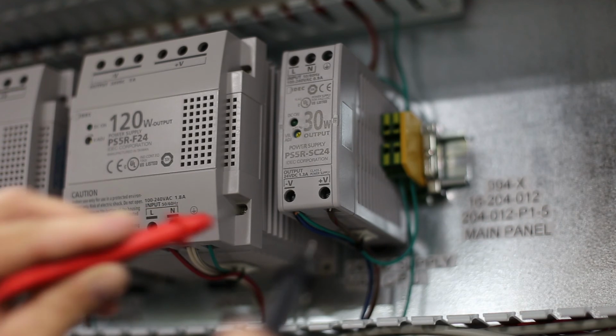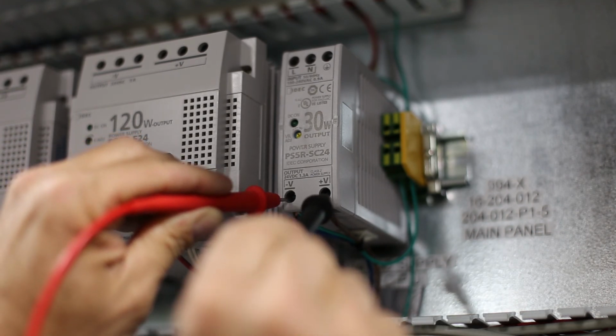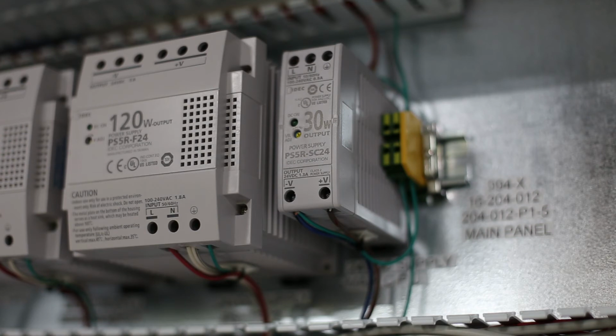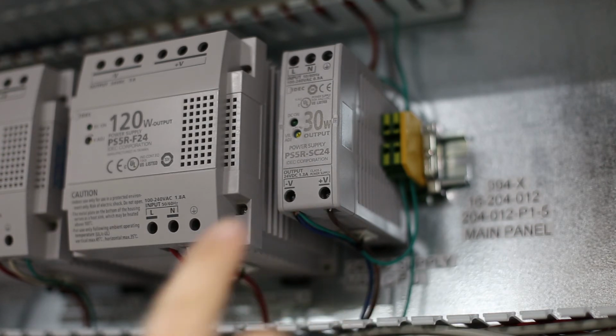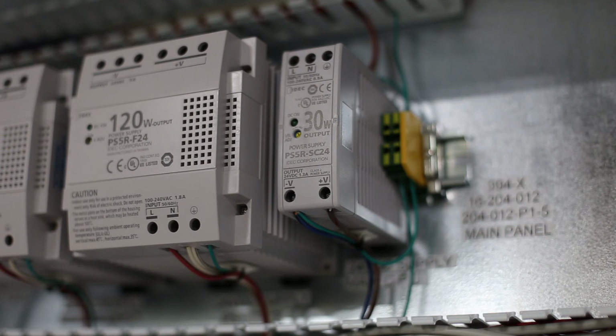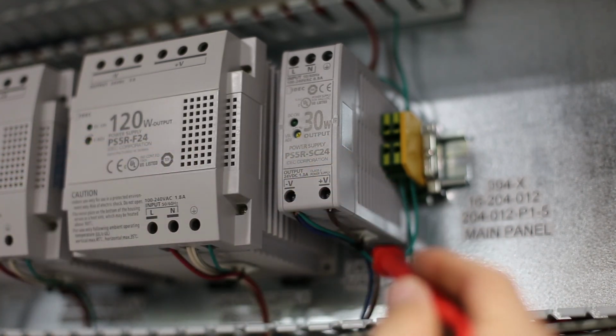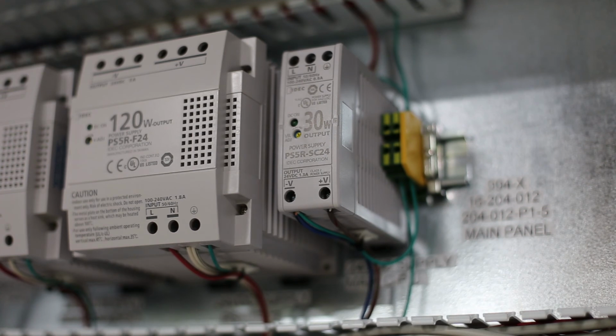You want to check for 24 volts on the bottom side here. Most likely it's going to be 0. What you want to do at that point in time is remove the DC plus wire. Once you remove the DC plus wire, check for voltage again and make sure you have 24 volts. If you have 24 volts now, what that tells you is your 24 volt DC plus is shorting out somewhere on your machine. 9 times out of 10, when it's shorted out, it means that you probably have an eye that's been damaged, and the eye's shorted out, and then at that point in time, it will take your 24 volt DC to ground, which will turn it out.